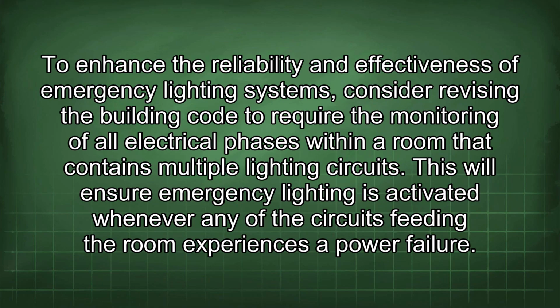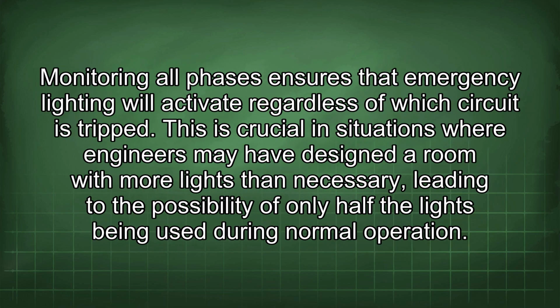To enhance the reliability and effectiveness of emergency lighting systems, consider revising the building code to require the monitoring of all electrical phases within a room that contains multiple lighting circuits. This will ensure emergency lighting is activated whenever any of the circuits feeding the room experiences a power failure. Monitoring all phases ensures that emergency lighting will activate regardless of which circuit is tripped.